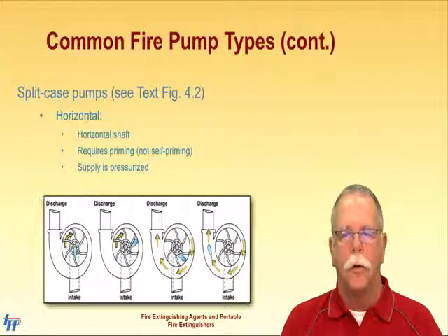Because the impeller on a horizontal split case pump is not fully submerged in water, it will require either that it is primed before use or that the supply be under pressure. This type of pump would be used to augment a municipal water system that is either inadequate in flow or pressure to perform at the standards required by an occupancy protection system.